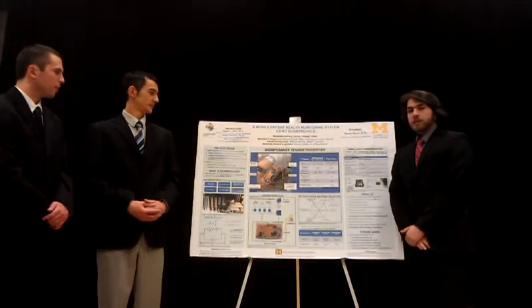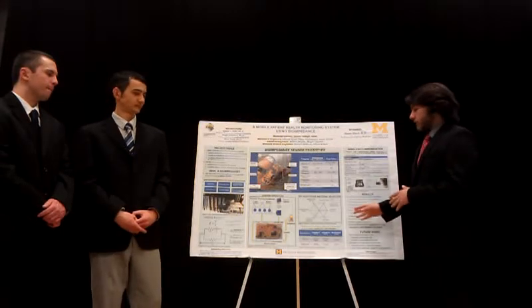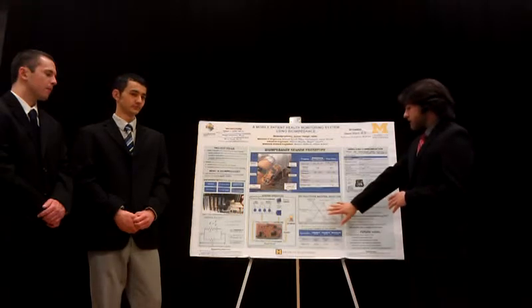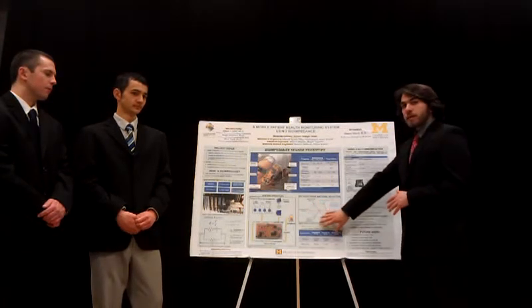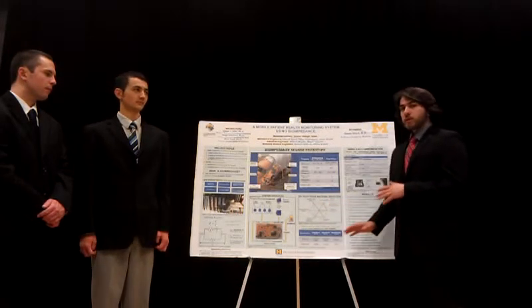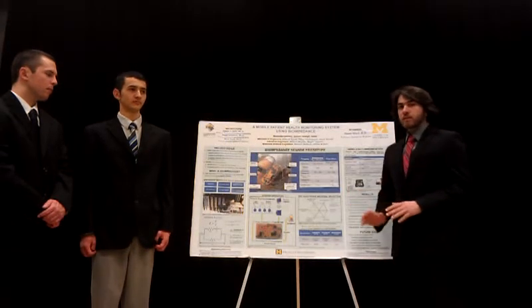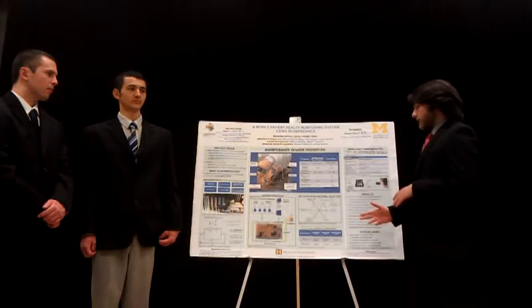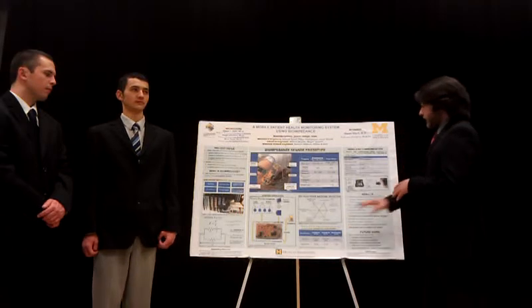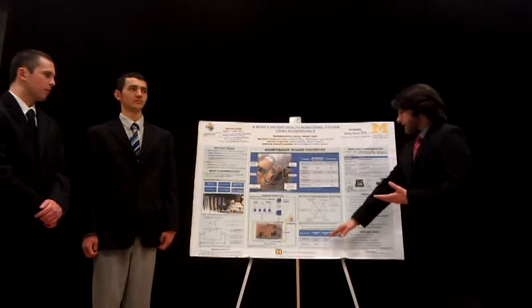For the dry electrode material selection, we started with 5 options of metals, according to our sponsor's requirement of having non-disposable electrodes. We compared them according to the criteria shown in this diagram. Platinum and gold were the best. However, they are very expensive, so we decided to go with stainless steel for the low cost and for the low contact impedance for the small diameters we're using. We then had 3 different electrodes for our sensor system to show to the customers or the sponsor.